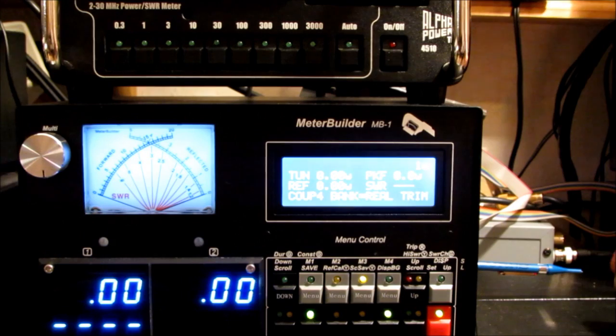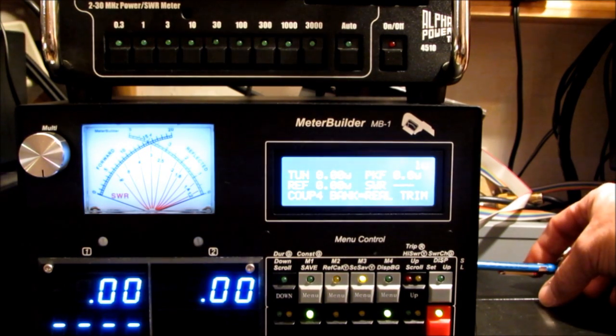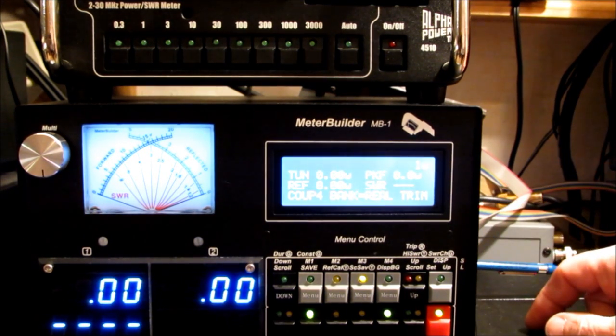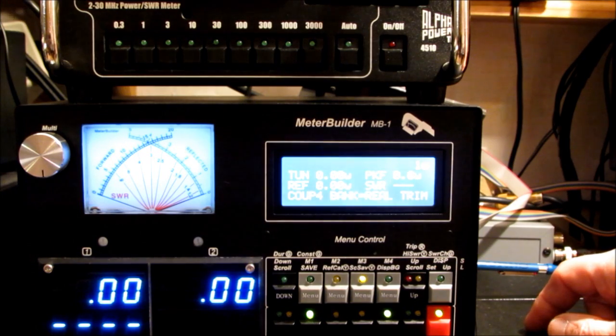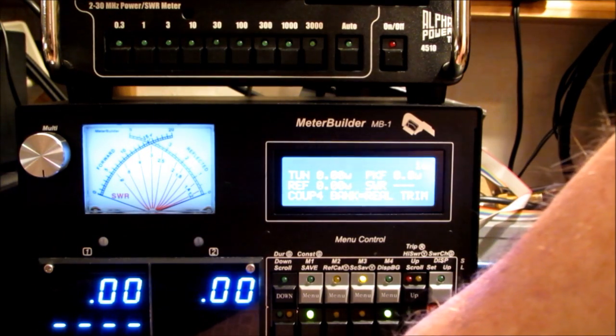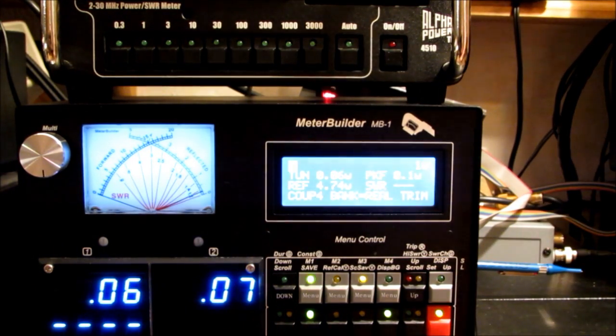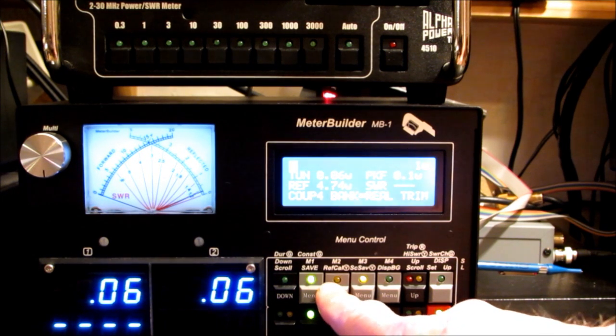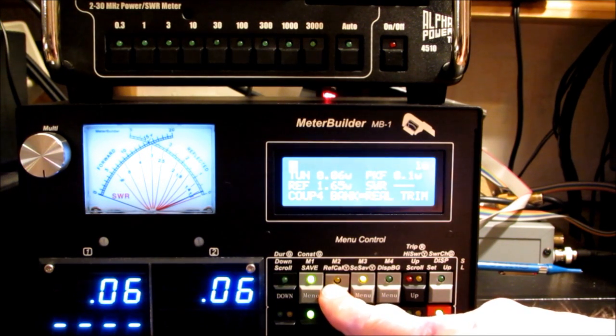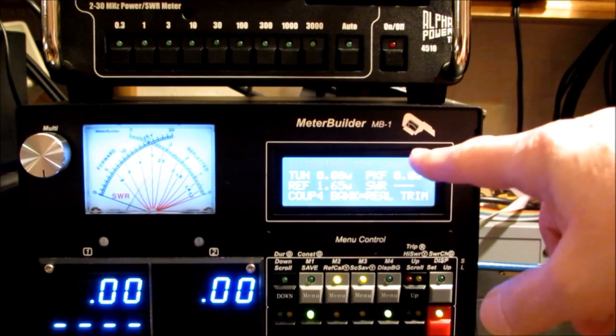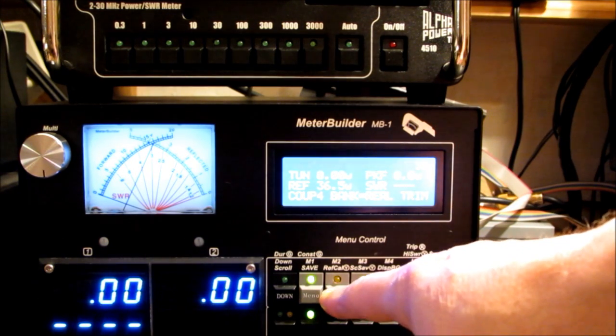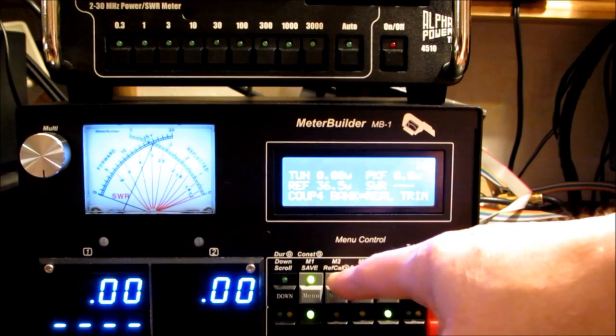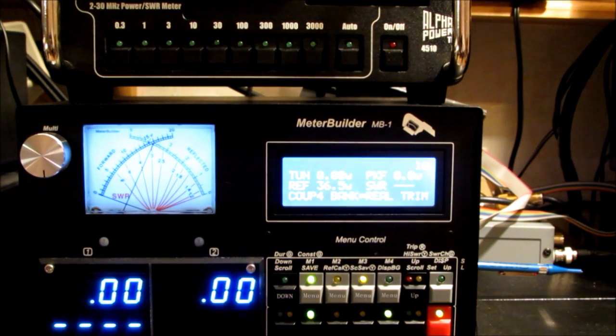You can see I have the adjustment stick in the trim pot for the reflected channel for coupler 4. Now let me go ahead and transmit my known power. What I have to do is place the meter in reflected channel calibration mode, done with a long push of this button. You don't have to memorize these - the silkscreen legends do a pretty good job of letting you know what the functions do.